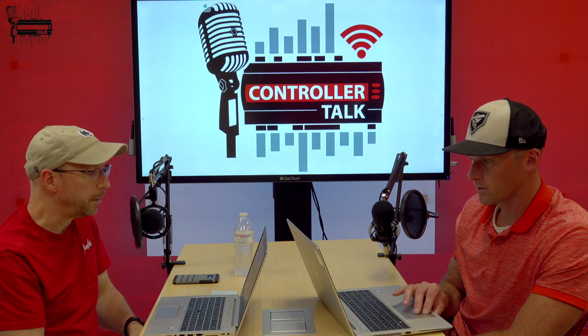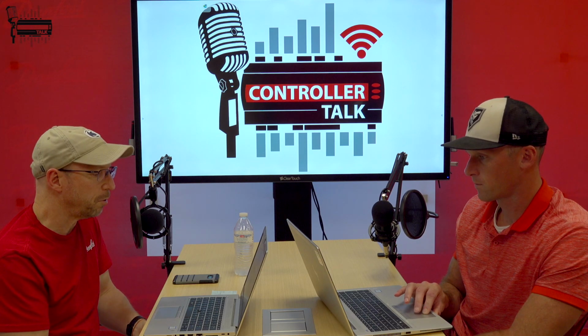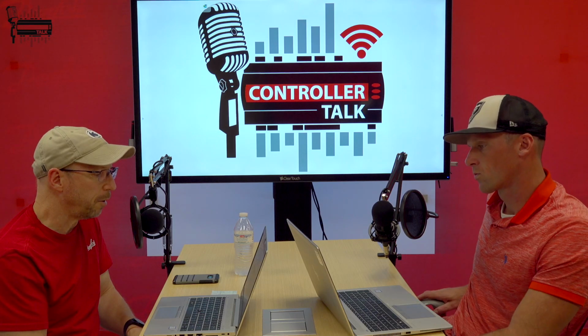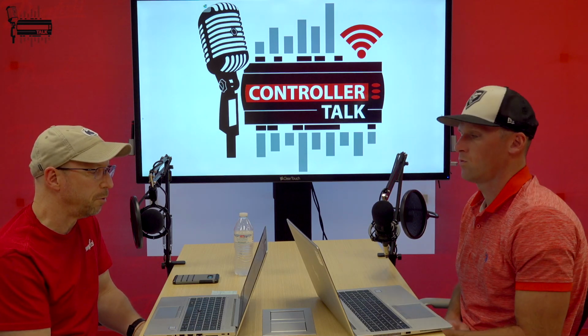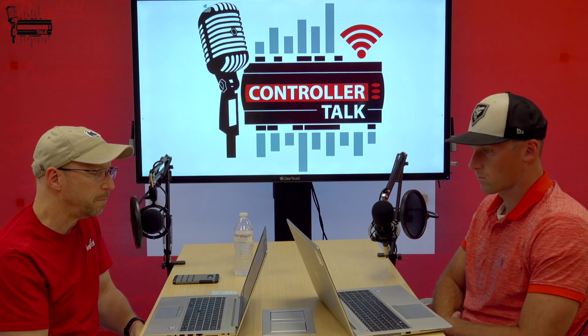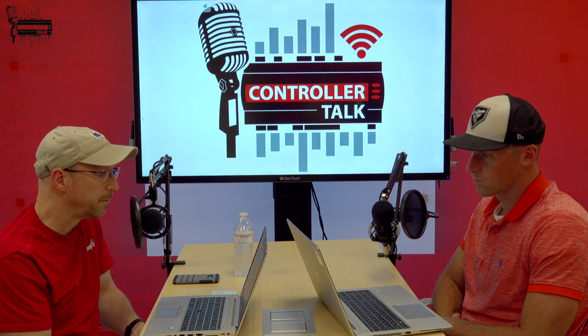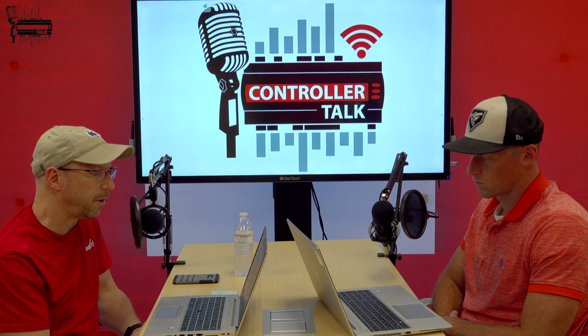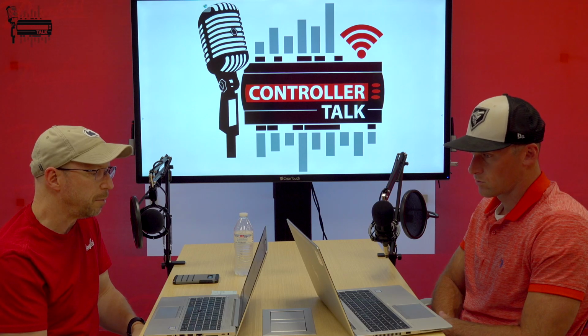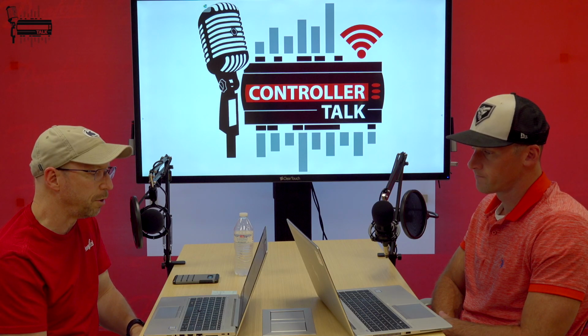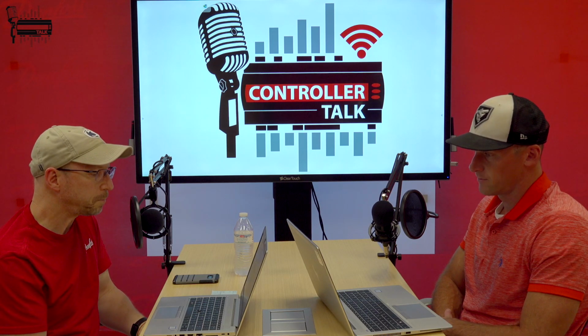Yep. All right, so let's start talking about pack controllers for CO2. There is one on the smaller side. The smallest pack controller we have for CO2 is the PC572, which has this kind of nickname as the mini pack controller. It can control 2 suction groups, and that's 3 and then 2 compressors, depending on how they're laid out. But you're looking at 2 suction groups with like 5 compressors altogether, with variable speed control options, of course. So heat reclaim is available along with control of the high pressure valve and the receiver bypass valve.